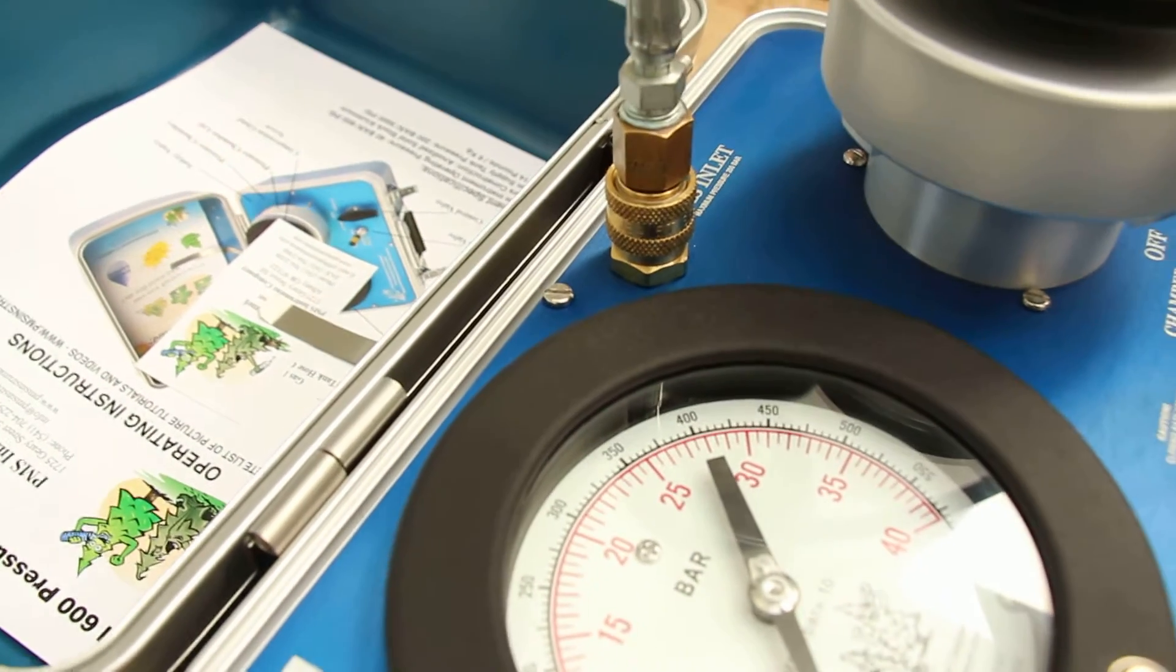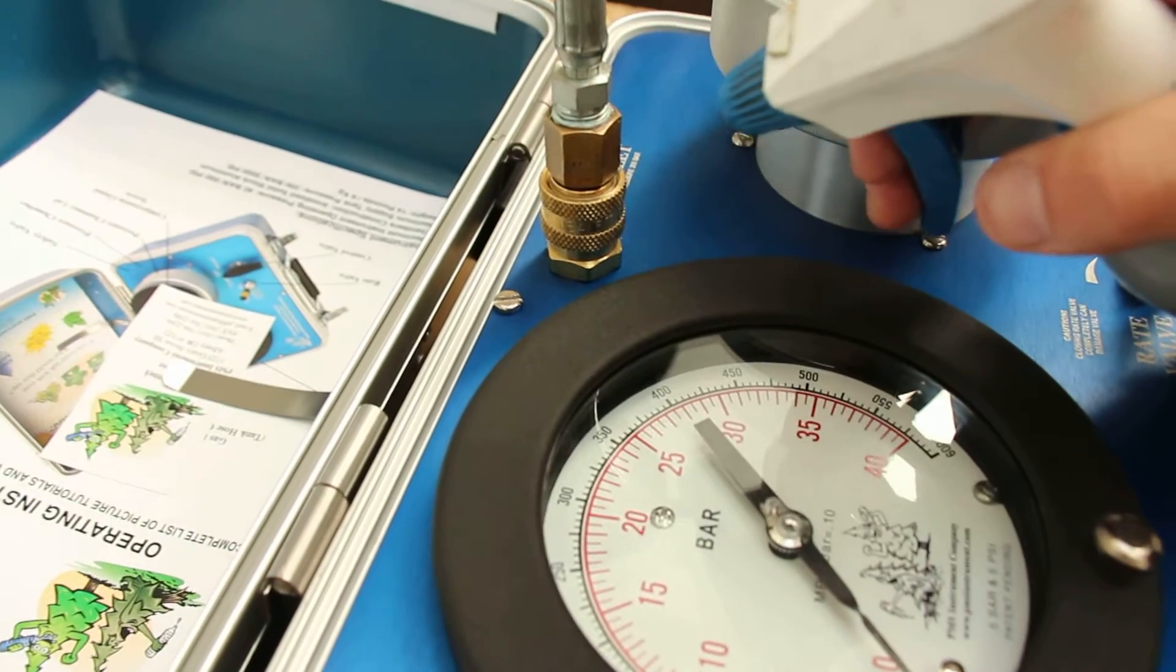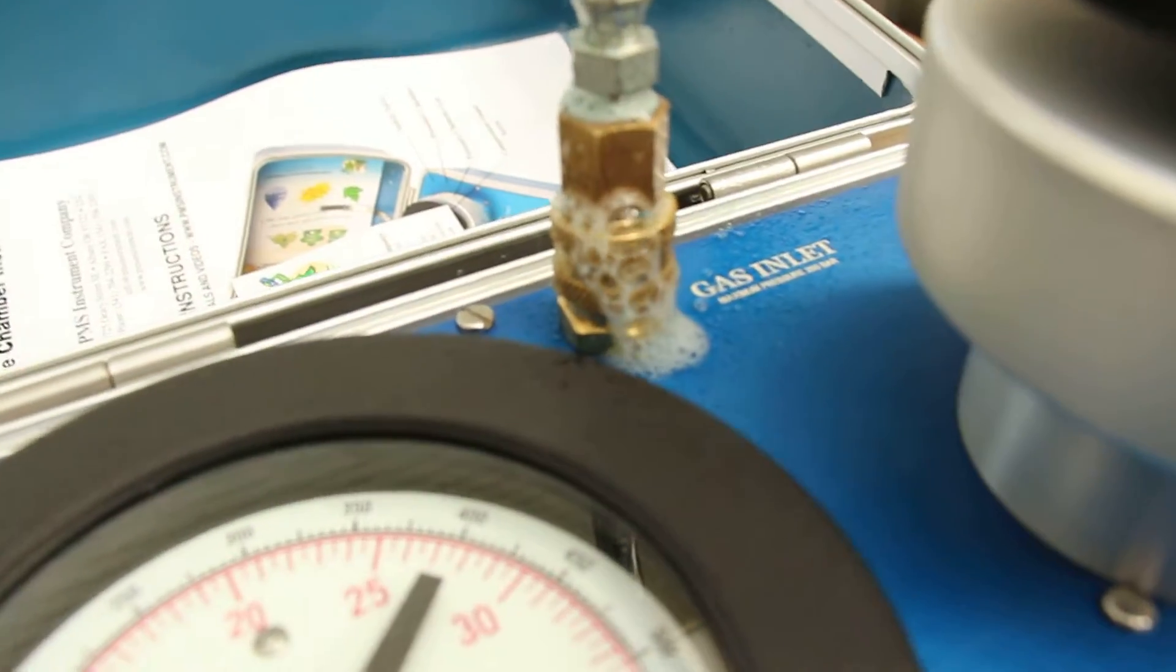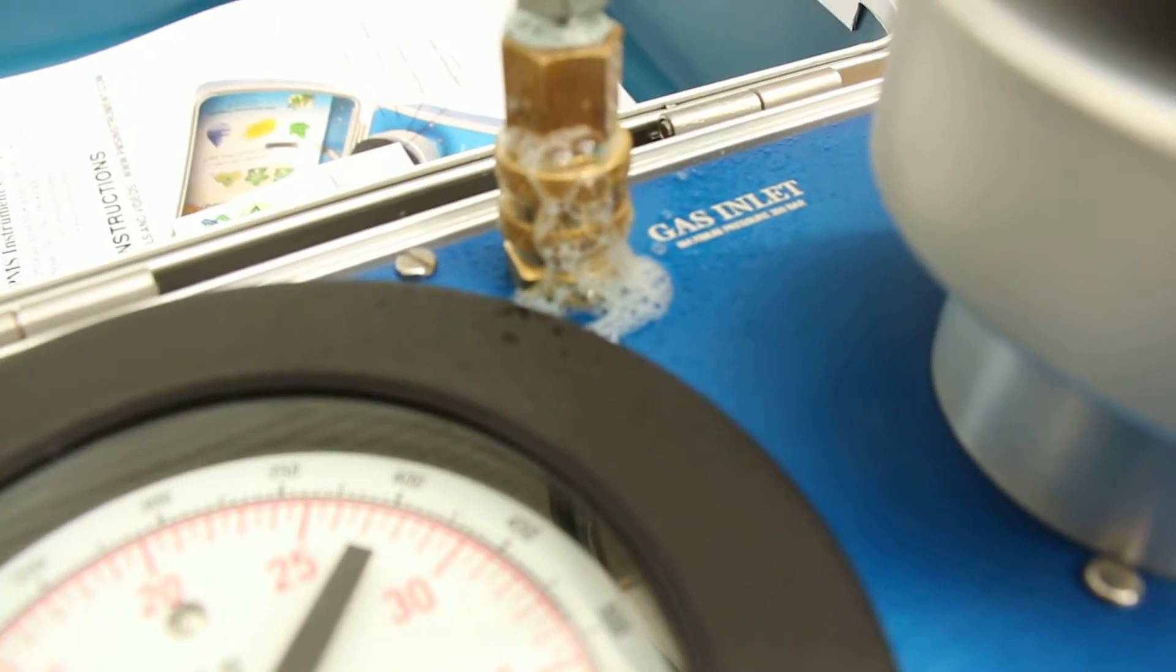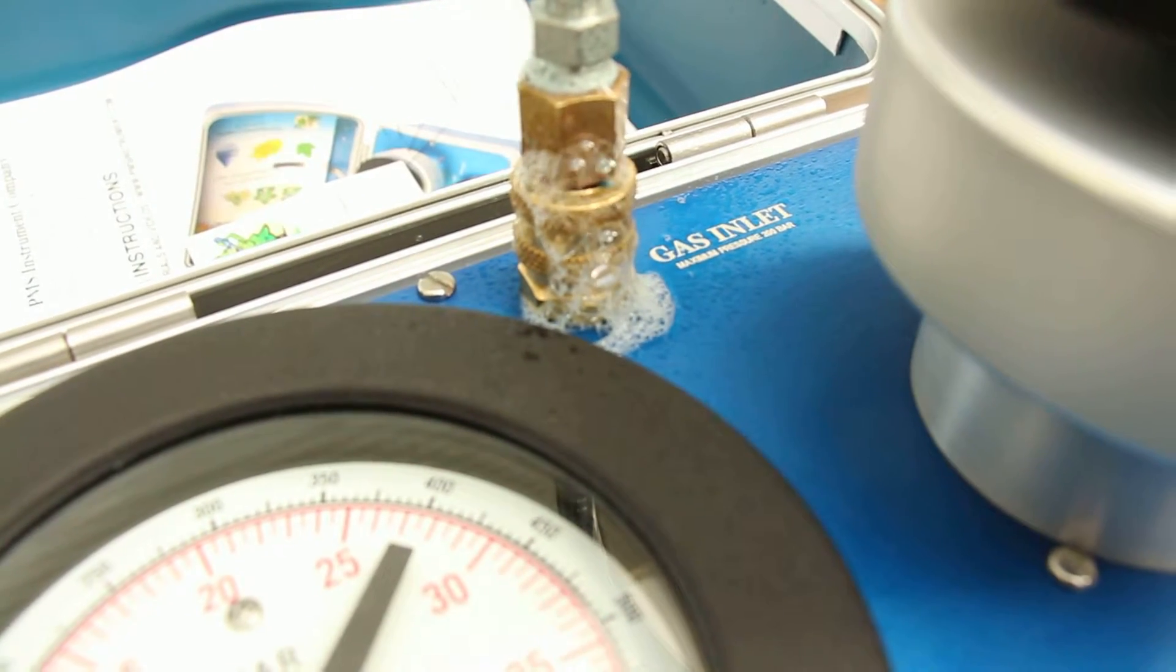But to ensure that we know for sure that it's a leak, the best thing you can do is use some sort of leak detector. Spray just a little bit of bubble check in there, and you can see we've got some pretty good bubbling going on right there. So there's definitely a leak there.